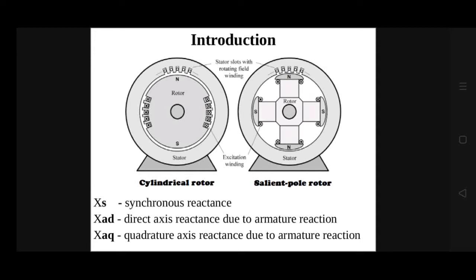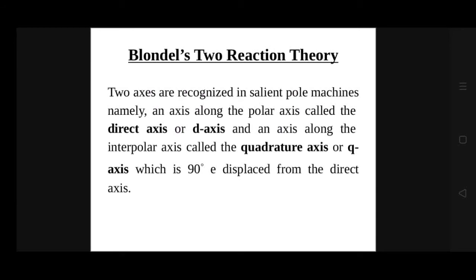These reactances are XAD, the direct axis reactance due to armature reaction, and XAQ, the quadrature axis reactance due to armature reaction. Consequently, the methods for finding voltage regulation of cylindrical rotor machines, when applied to salient pole machines, give incorrect results. In salient pole machines, regulation is found by applying Blondel's two reaction theory. According to this theory, two axes are recognized: the direct axis or D-axis along the polar axis, and the quadrature axis or Q-axis along the interpolar axis, which is 90 degrees electrically displaced from the direct axis.